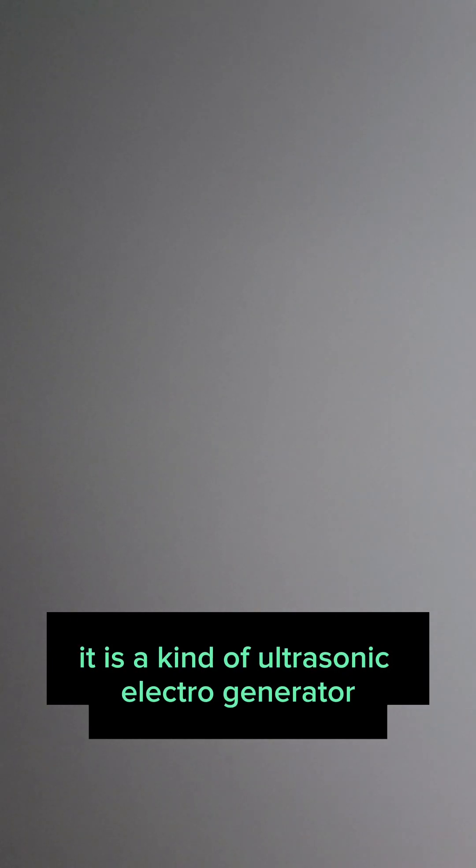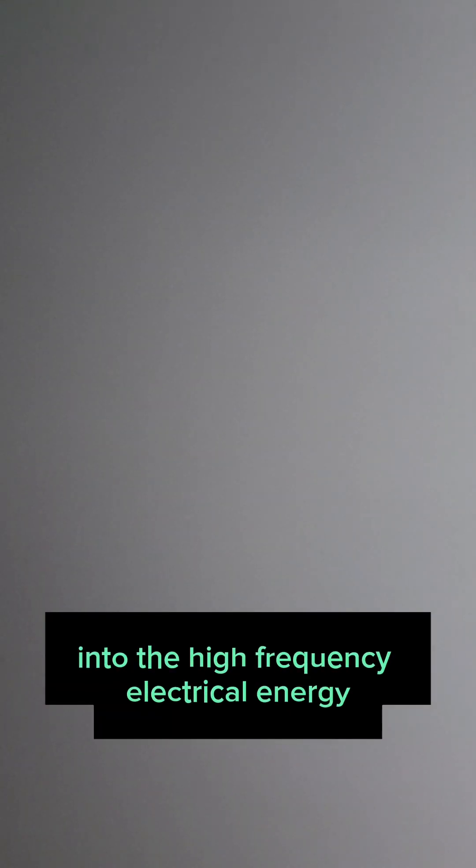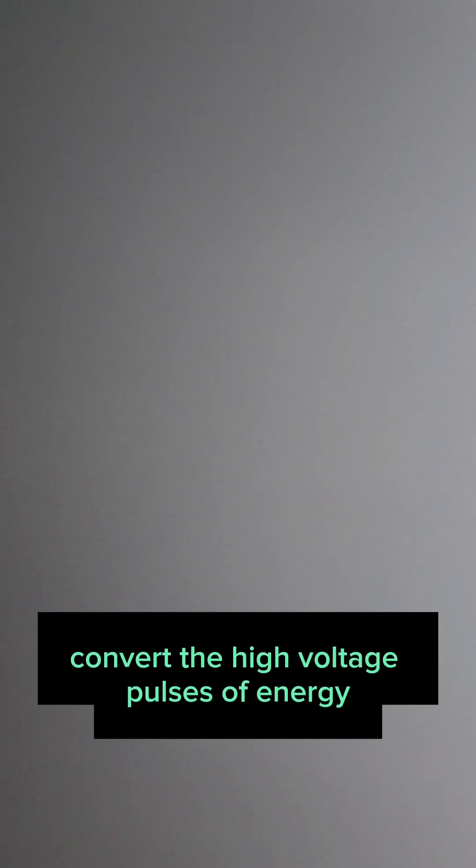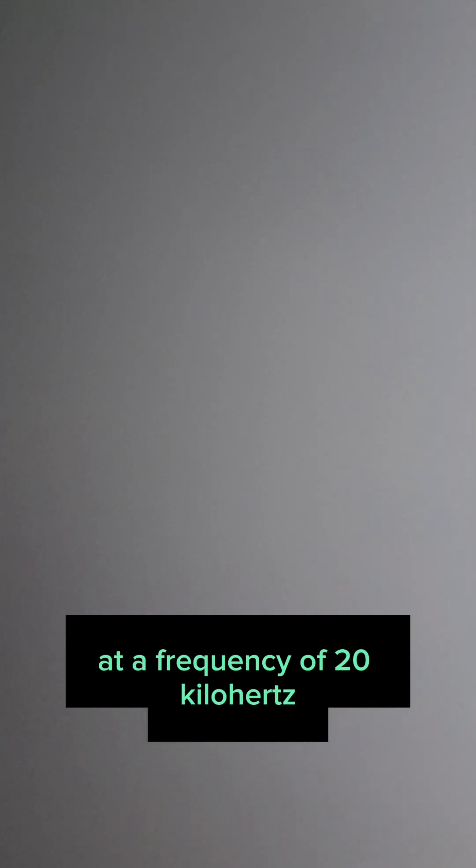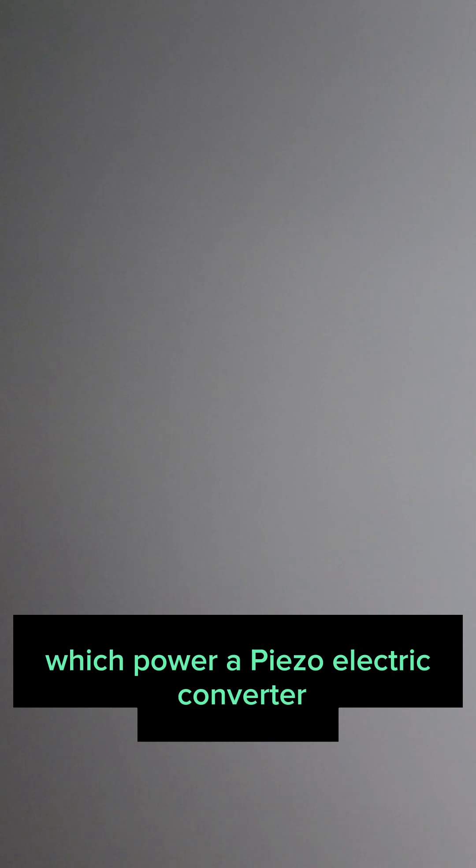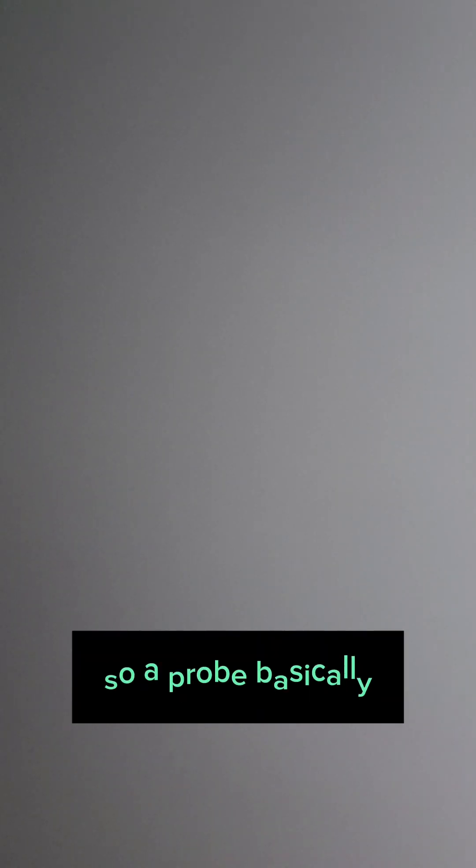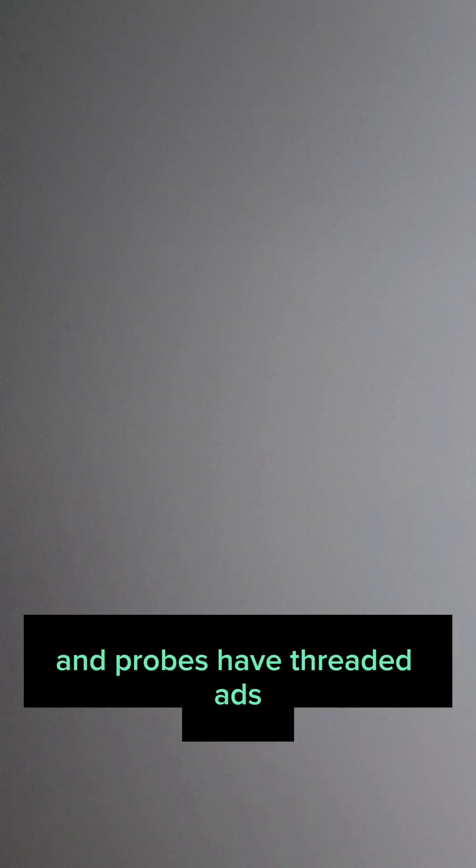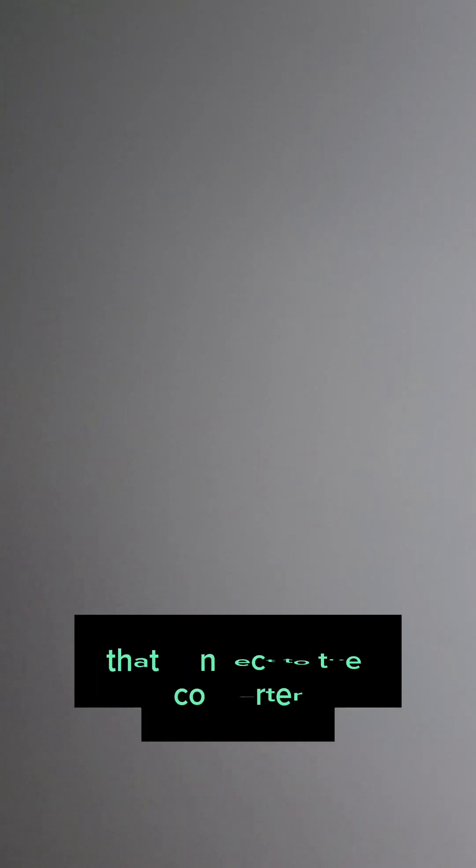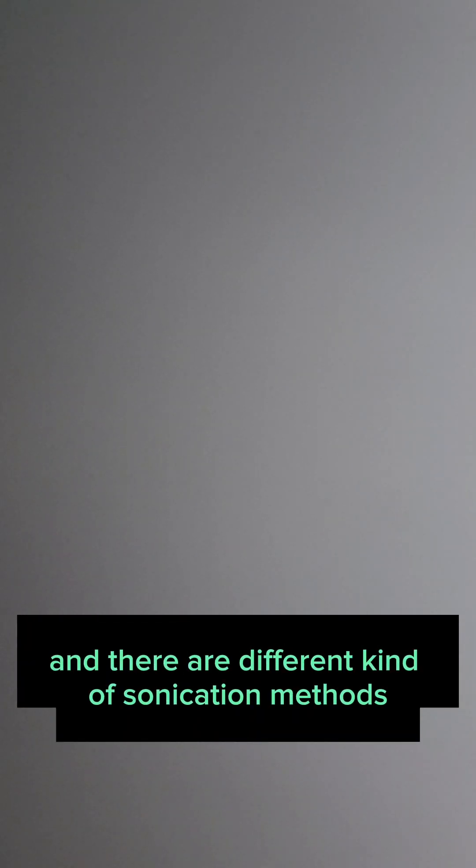There are different parts of the sonicator. We have the generator. The generator is a kind of ultrasonic electric generator that will convert alternating current into high frequency electrical energy. The converter will convert the high voltage pulses of energy at a frequency of 20 kilohertz, which power a piezoelectric converter. And then we have a probe. The vibration will be amplified as well as transmitted down the probe line. Probes have threaded ends that connect to the converter. During the operation, the probe's tip expands and contracts longitudinally.